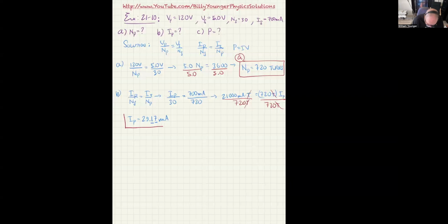So that's the current that comes in. Notice by having 29 milliamps coming in, we actually stepped up the current, even though this is not called a step-up transformer. Step-up transformers mean you're increasing the voltage, and step-down transformers mean you're decreasing the voltage. Their names are based on voltage, not on current. So this one stepped up the current from 29 milliamps on the primary to 700 milliamps on the secondary.